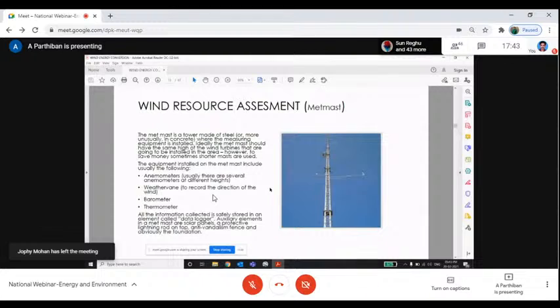The anemometer is used to measure wind speed, how much wind is blowing in the particular area. And the wind vane shows which direction the wind is blowing. For example, from April to September it will be in one direction, and after that there will be a directional change. Only in peak wind season will it be nearly maximum in a single direction, even though there is a small angle difference. But in the non-peak seasons, it will differ in each direction. The wind will blow from north, east or south. So for calculating wind direction, the wind vane is used. And the barometer and thermometer are for air density and temperature measurement.